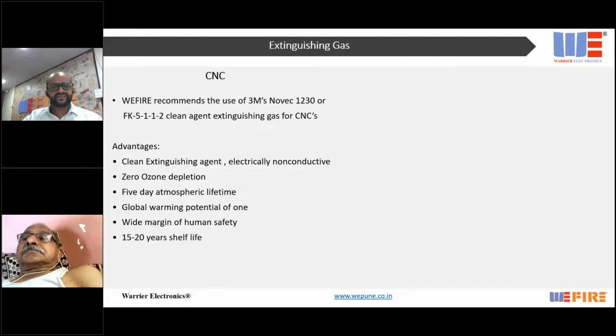So a few of the advantages which I can mention: it's a clean extinguishing gas. It's electrically non-conducting. It has zero ozone depletion potential, only a 5-day atmospheric lifetime, and a global warming potential of 1. It has the widest margin of human safety across all the extinguishing gases available in the market as of date. And the best advantage is it has a shelf life of 15 to 20 years. Unless your system gets discharged on its own, you do not have to replace the gas. The only thing that you need to do is hydro test the cylinders every 5 years as per the government norms, and you can refill the same gas and reuse it.